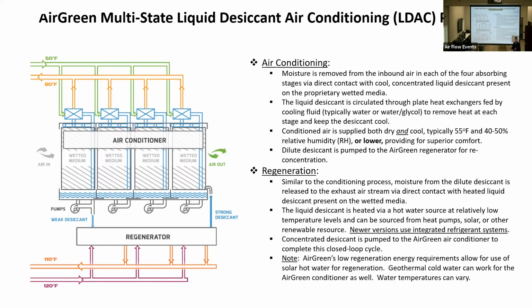Now, if you have excess hot water energy, then you have to deal with that in some of our applications. We've put a dry cooler in the hot water loop to shed hot water heat so that we can get continuous chilled water flow. We build these where the media comes in pre-fabricated cassettes too. So after 2 to 3 years of service, if that gets fouled and dirty, you can just replace those. And those are not high dollar items.